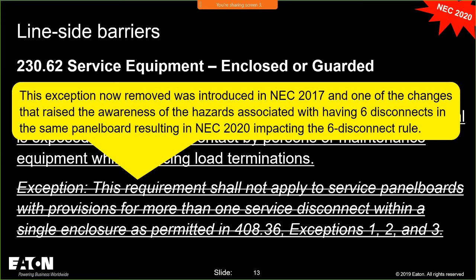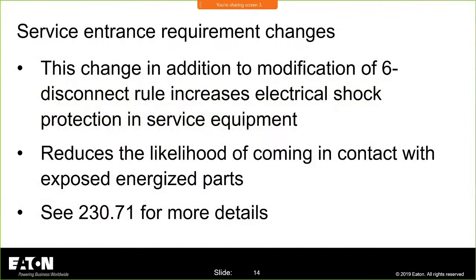This was what they removed. Remember, there was an exception in the 17 cycle that said the requirement of these barriers did not apply to service panel boards with provisions for more than one service disconnect. That is what changed the 6 disconnect rule. That is what changed these barriers. And there was an elevated awareness that we're going to require this barrier when we have a main breaker, but we have this huge hazard of 6 disconnects in a panel board that we're not addressing. But that has been addressed in this cycle. We're going to probably talk about that next.